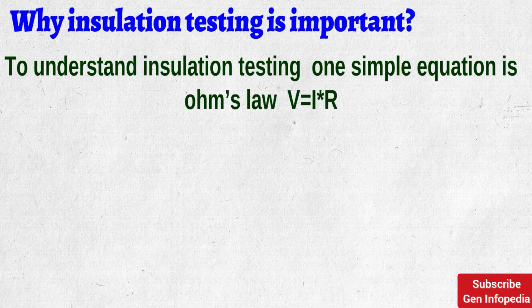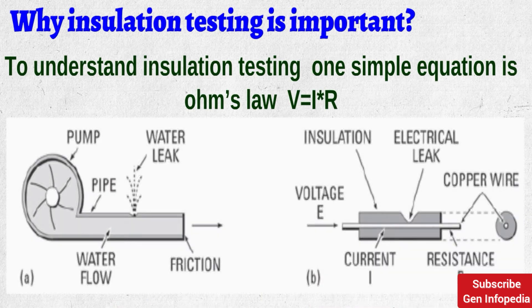To understand insulation testing, one simple equation is Ohm's Law: V = I × R. If the resistance of the insulation material increases, it automatically resists the current and keeps it in its path along the conductor. But if the resistance of the insulator decreases, there is some leakage current between the conductor and ground — as shown in figure B.